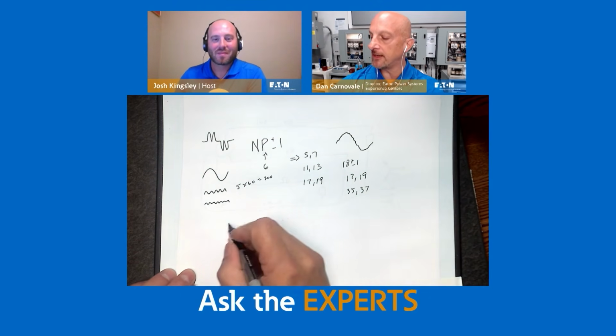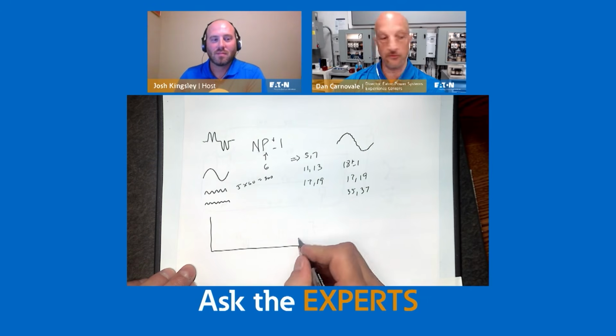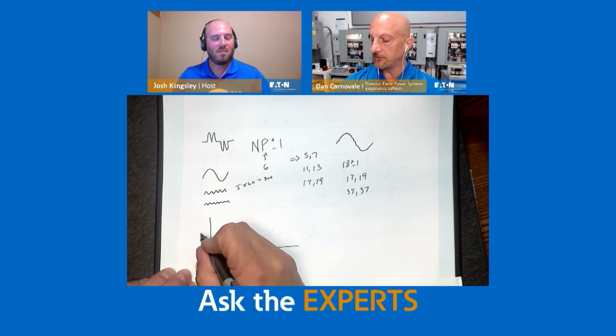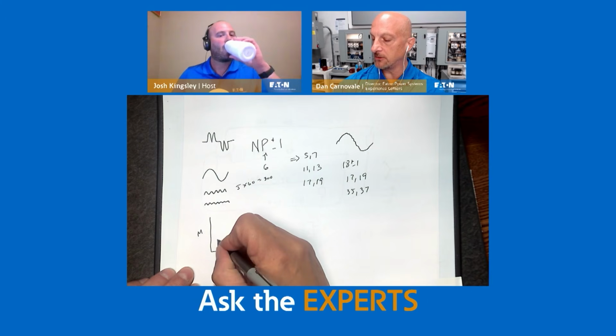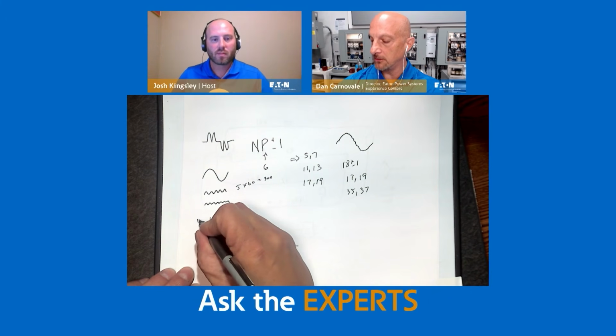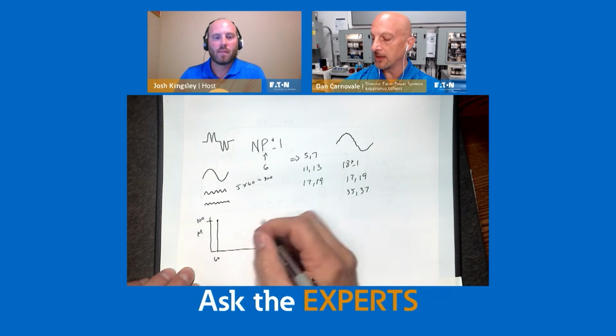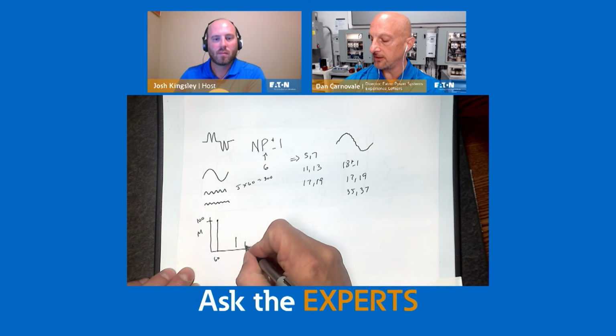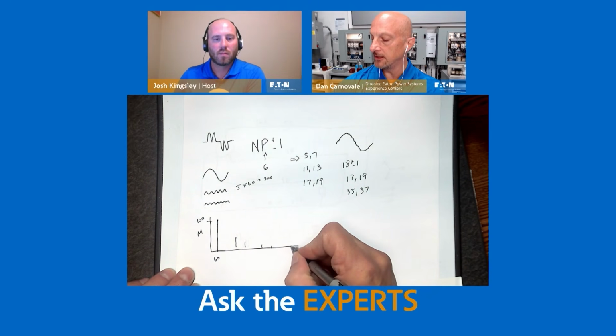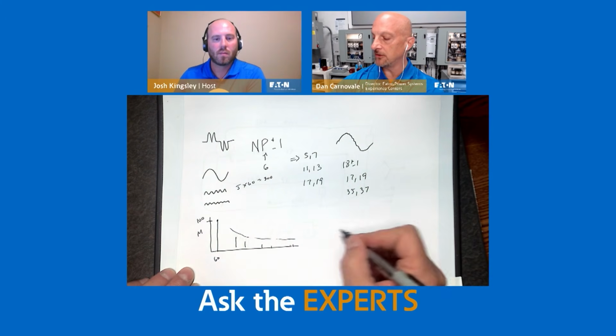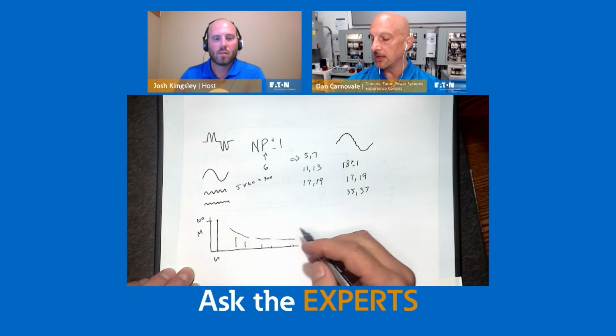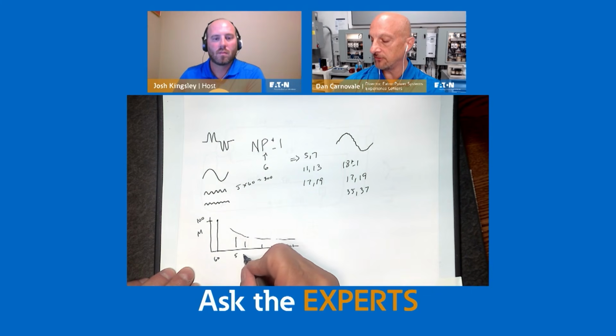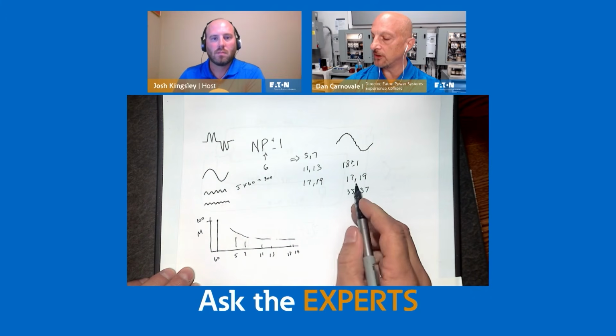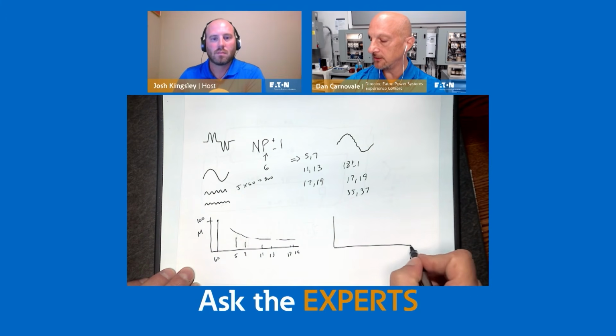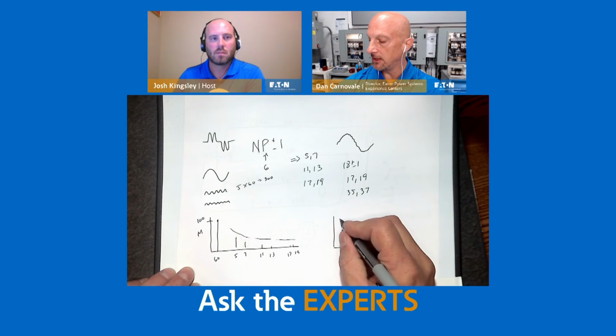But anyway, when I do all that and I look at the frequency spectrum, so if this is magnitude, and we'll call the fundamental 100%, the fundamental being 60 hertz, I would have 5th and 7th and 11th and 13th and 17th and 19th. What you notice is that as the frequencies go up, the magnitude of the harmonic goes down. So this is 5th, 7th, 11th, 13th, 17th, 19th, and so forth. Now, when I draw the spectrum for just the 18 pulse drive, I still have my fundamental.